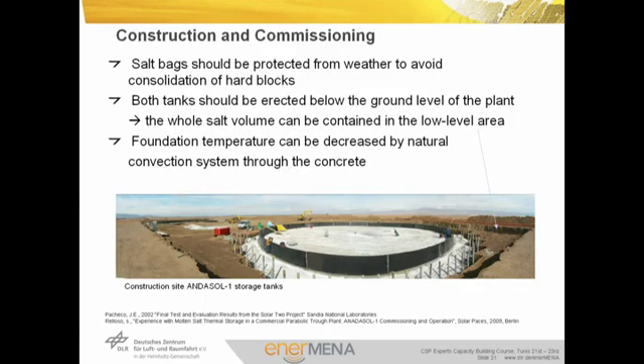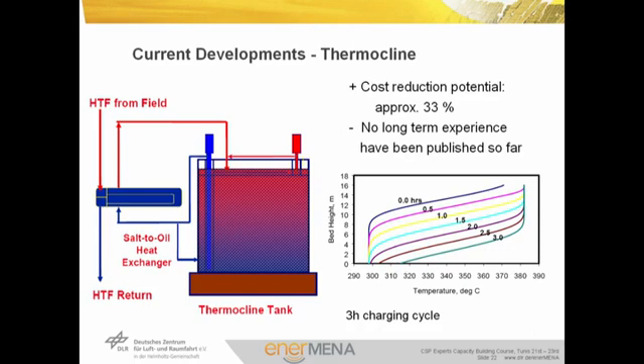Specific aspects must be considered during the construction of the tanks and foundations. Molten salt is delivered in large bags which must be stored near the construction site, and care must be taken to avoid consolidation into hard blocks. Both tanks should be erected below ground, since in case of leakage the whole salt volume should be contained in the low-level area. The concrete foundation should not be at temperatures exceeding 100 degrees, so the temperature can be decreased by natural or forced convection systems. The main costs of a two-tank molten salt system result from the cost of the molten salt, and an alternative is to replace part of the molten salt with a cheaper filling material.